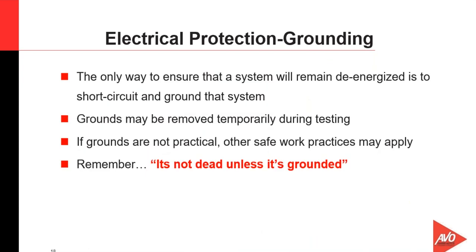To protect workers in the test area and to ensure that the cable system that we're going to test is actually de-energized, the only way to ensure that is to actually verify it and then short circuit and ground the systems. These PPE grounds need to be rated. They need to be engineered basically to withstand any type of short circuit current or duration of short circuit that might be imposed on them. The grounds need to be installed in a method of equipotential where the worker is not exposed to any separation of potentials in case an accidental activation occurred.